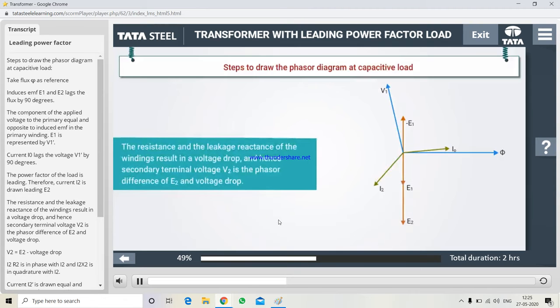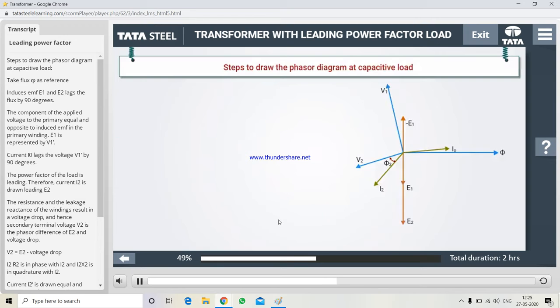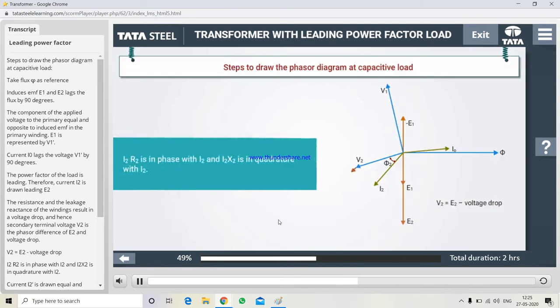The resistance and the leakage reactance of the windings result in a voltage drop, and hence the secondary terminal voltage V2 is the phasor difference of E2 and the voltage drop. V2 equals E2 minus the voltage drop. I2R2 is in phase with I2 and I2X2 is in quadrature with I2.